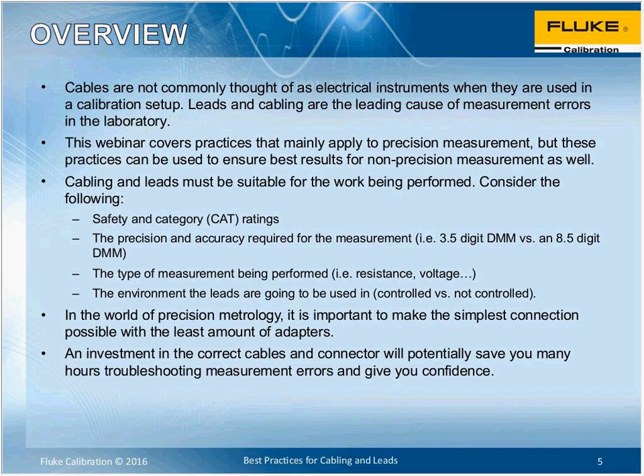One of the things I'd like to lead into, no pun intended, is what you need before you start the work. You look at your cabling setup, and you need to make sure it's considered as part of the entire calibration setup. What are some things you should be thinking about when you start looking at your leads? One, you want to make sure that they're safe. All leads that you'll use have some sort of maximum voltage or current rating, and you want to make sure that it's going to be safe for the application. There are also additional what they call category ratings. These are measurement category ratings, and usually they're from 1 to 4, or 1 to 5, I think it is now.